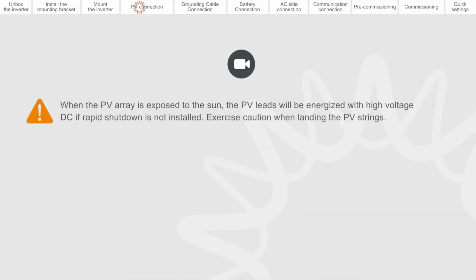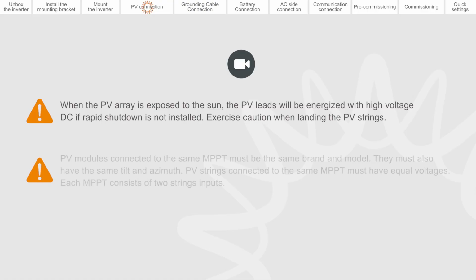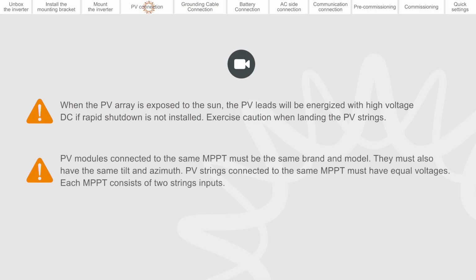When the PV array is exposed to the sun, the PV leads will be energized with high voltage DC if rapid shutdown is not installed. Exercise caution when landing the PV strings. PV modules connected to the same MPPT must be the same brand and model. They must also have the same tilt and azimuth. PV strings connected to the same MPPT must have equal voltages. Each MPPT consists of 2 string inputs.